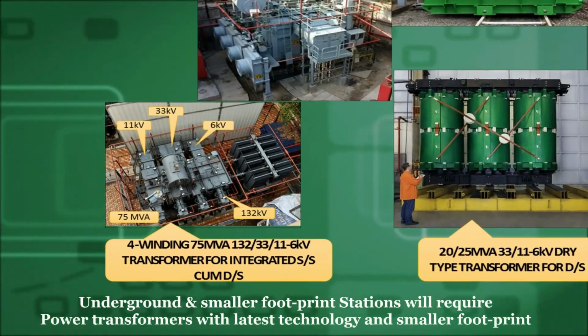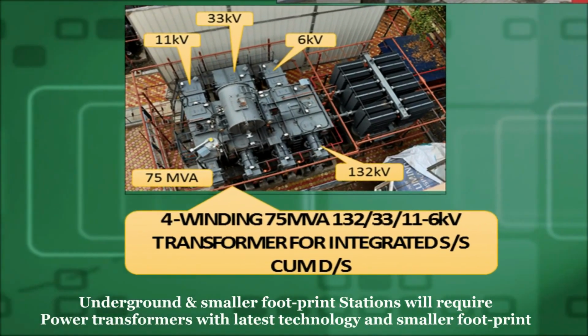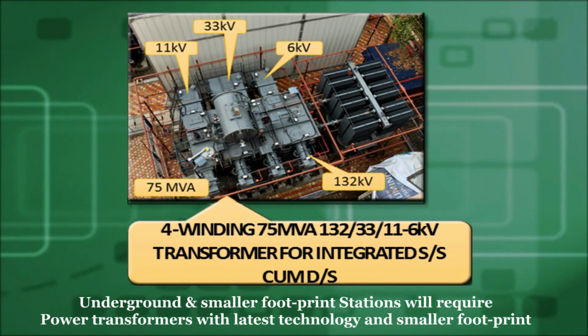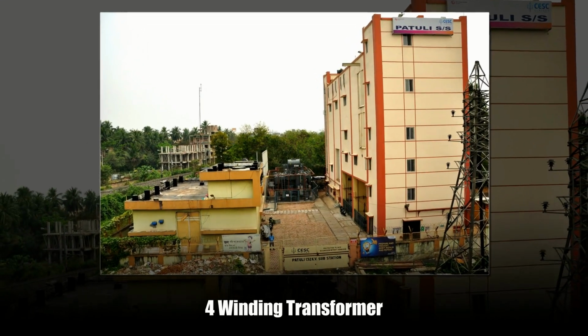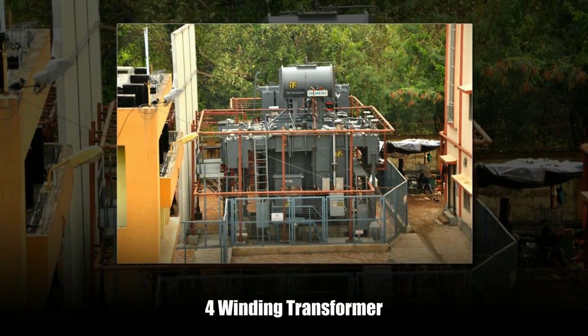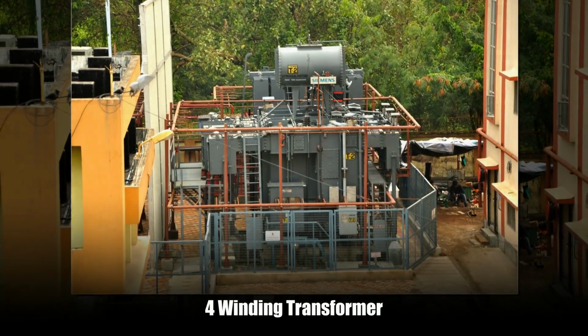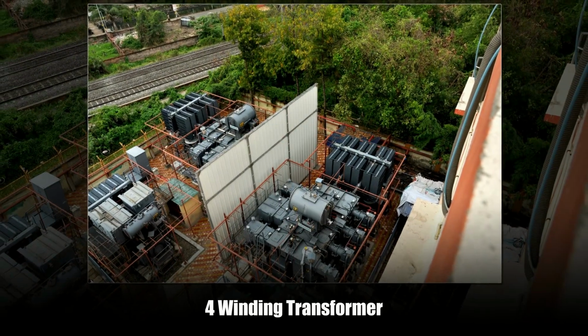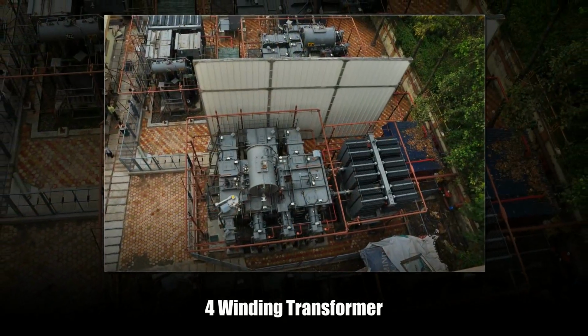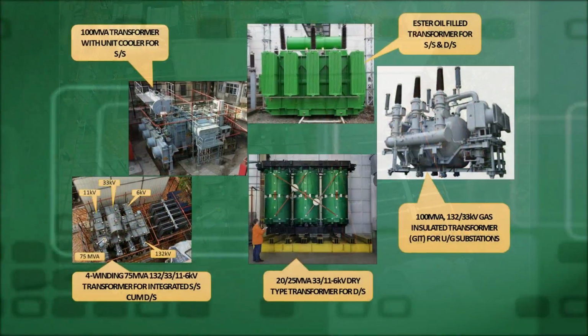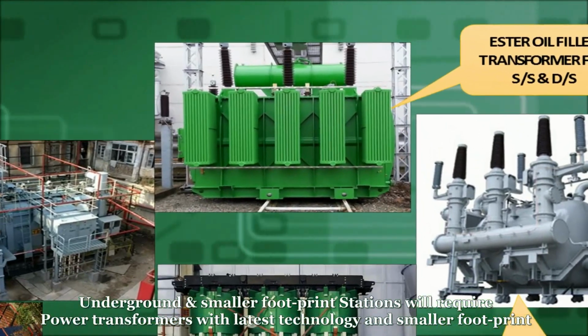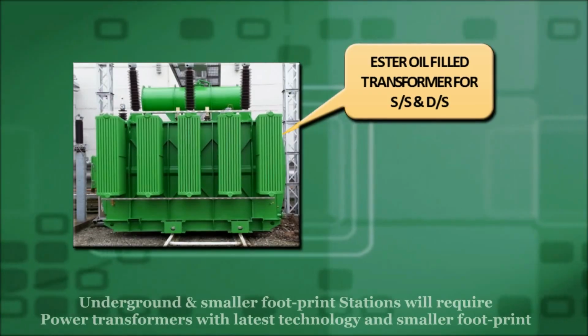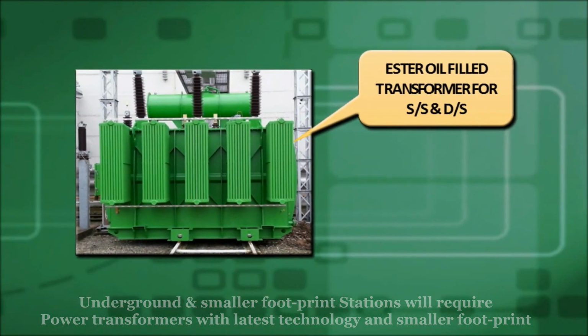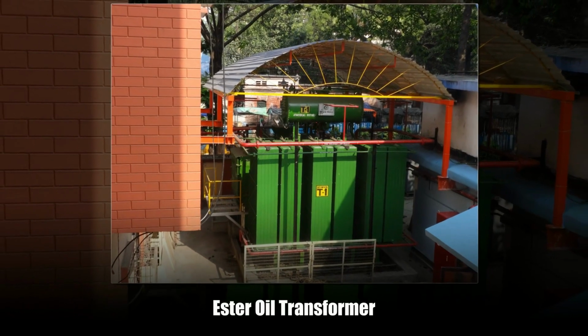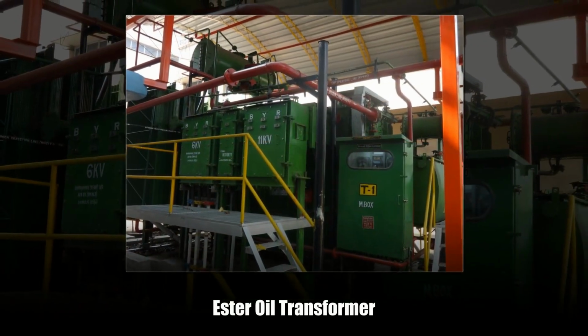Four-winding transformers, a new concept in power distribution, installed at Patuli substation, integrate the 132 by 33 kV system of the substation with the 33 by 11/6 kV distribution station within a single premise, thereby optimizing space and cost. This unique solution is effective for city-based utilities, where space availability is critical. Ester oil has a high flash point with a lower carbon footprint. Transformers with ester oil can have high overloading capacity as compared to mineral oil transformers. CESC initiated installation of ester oil-filled 20 MVA transformers at a few distribution stations.